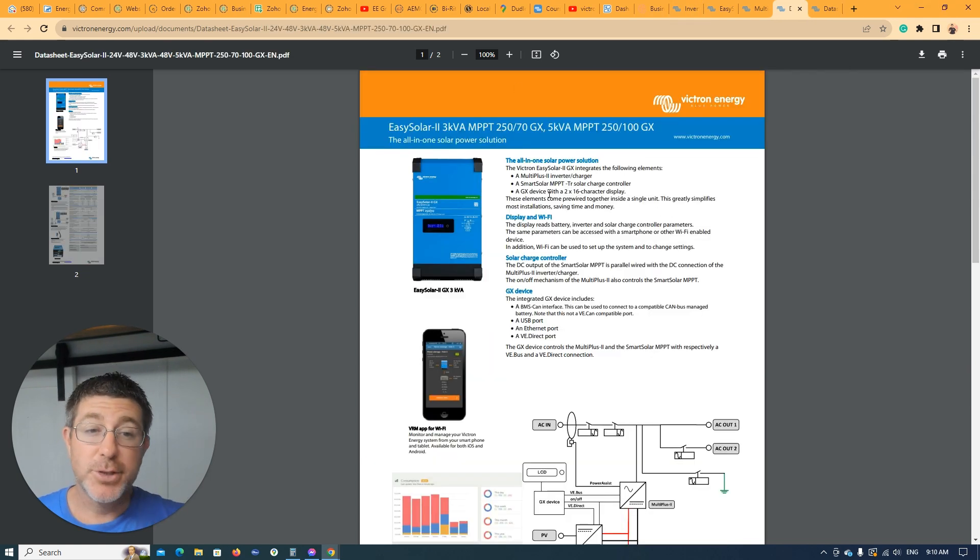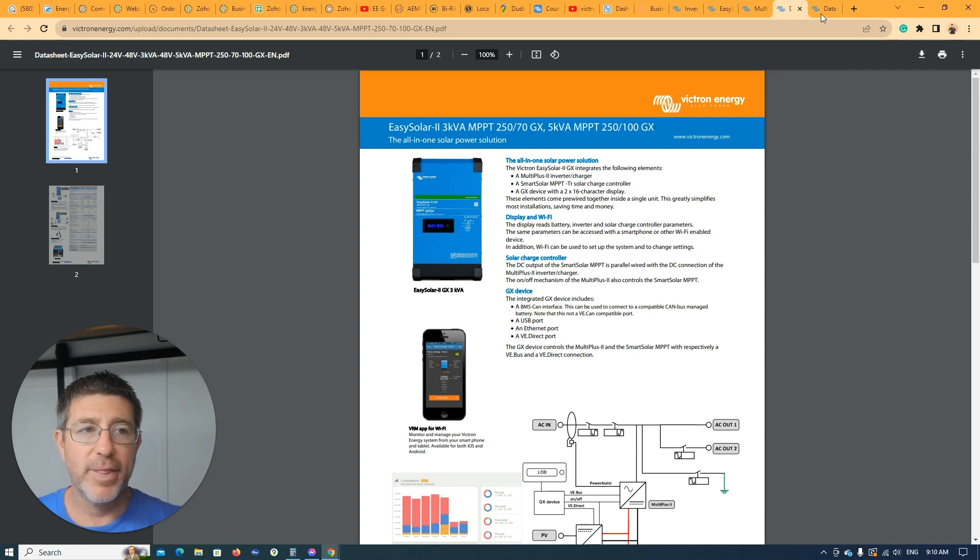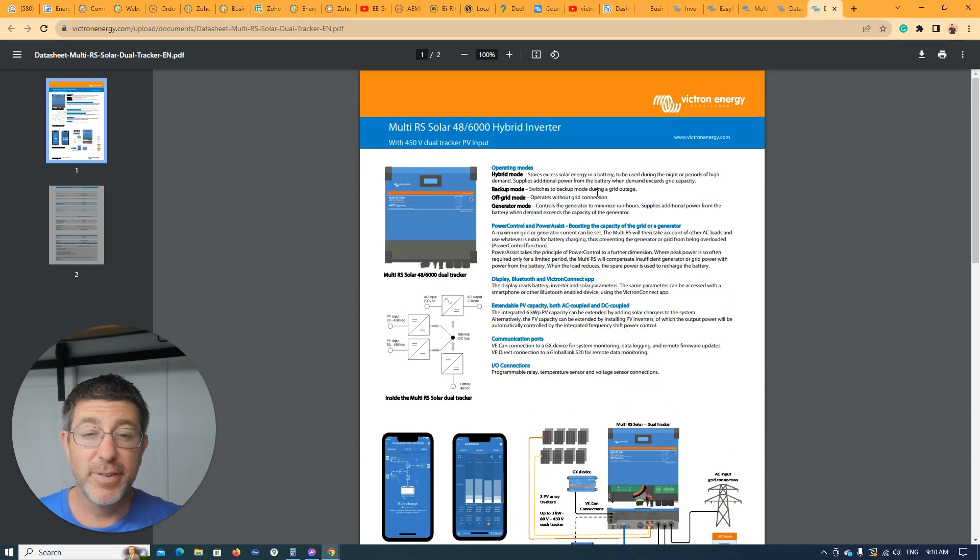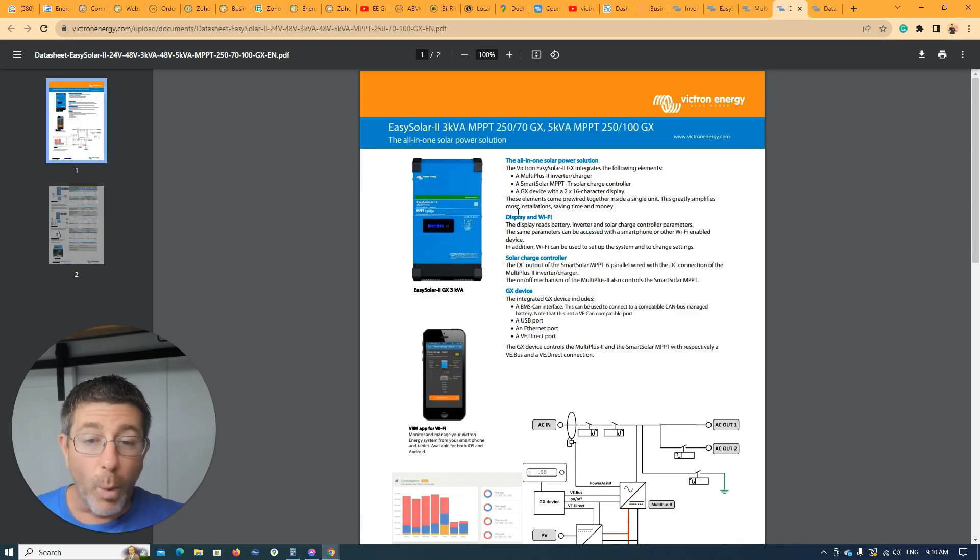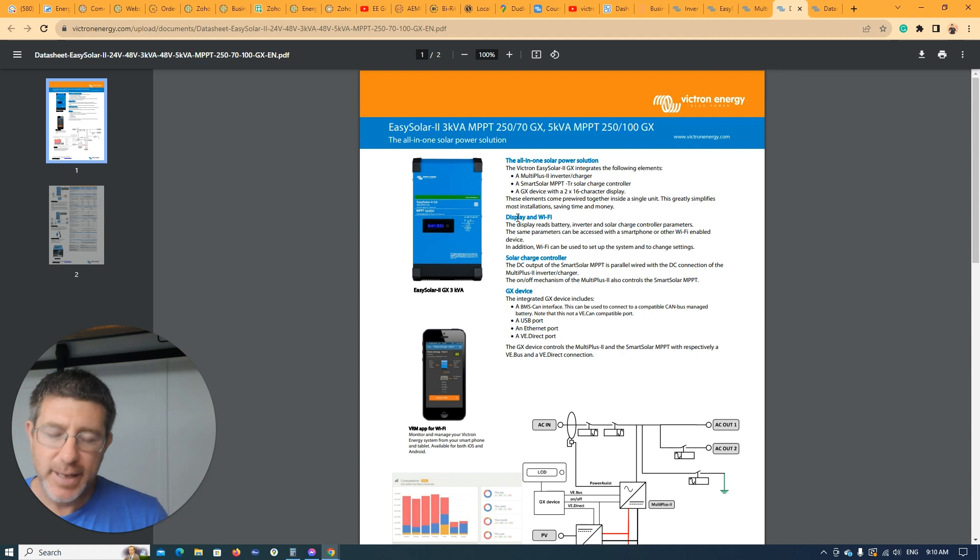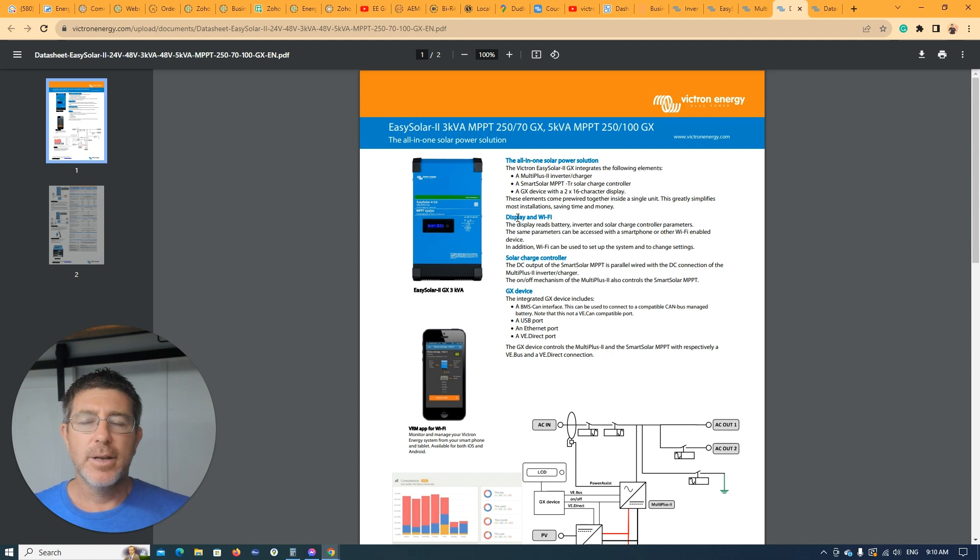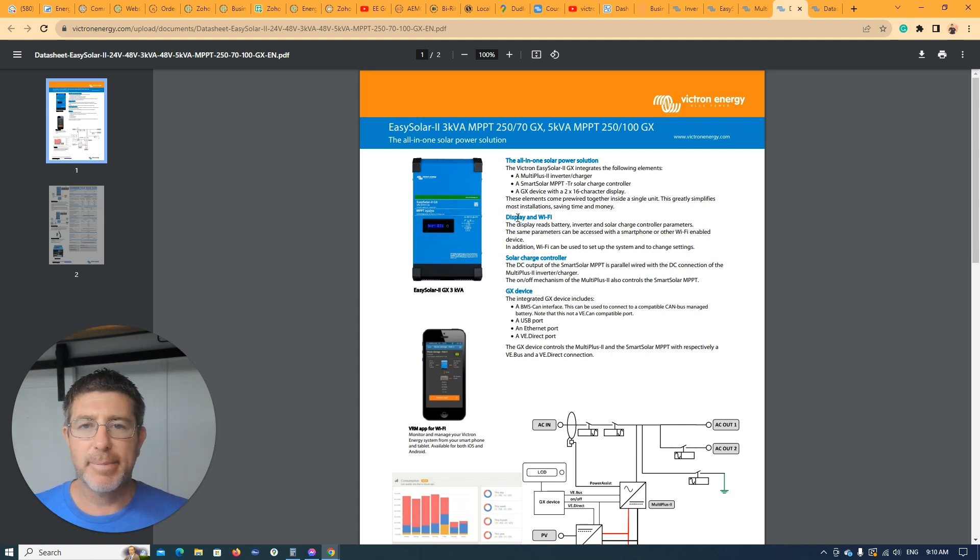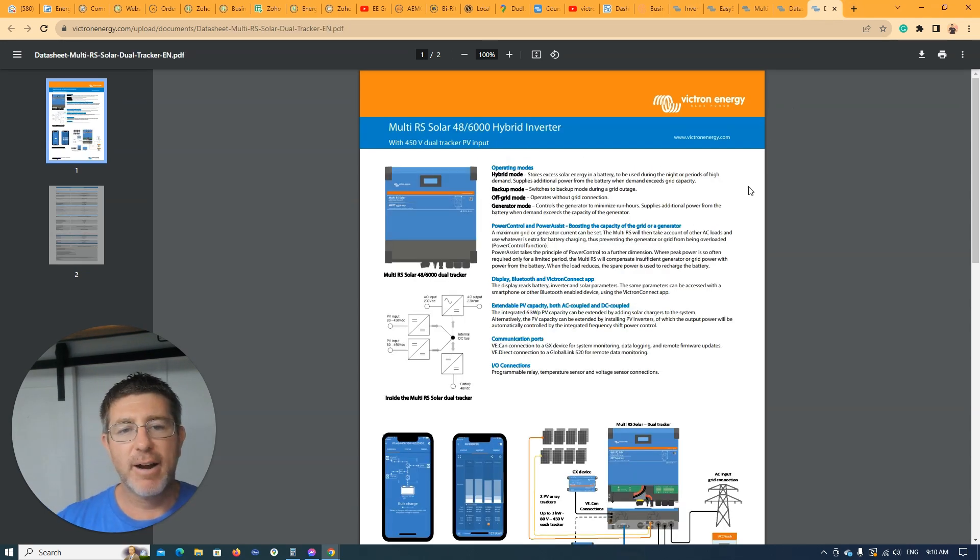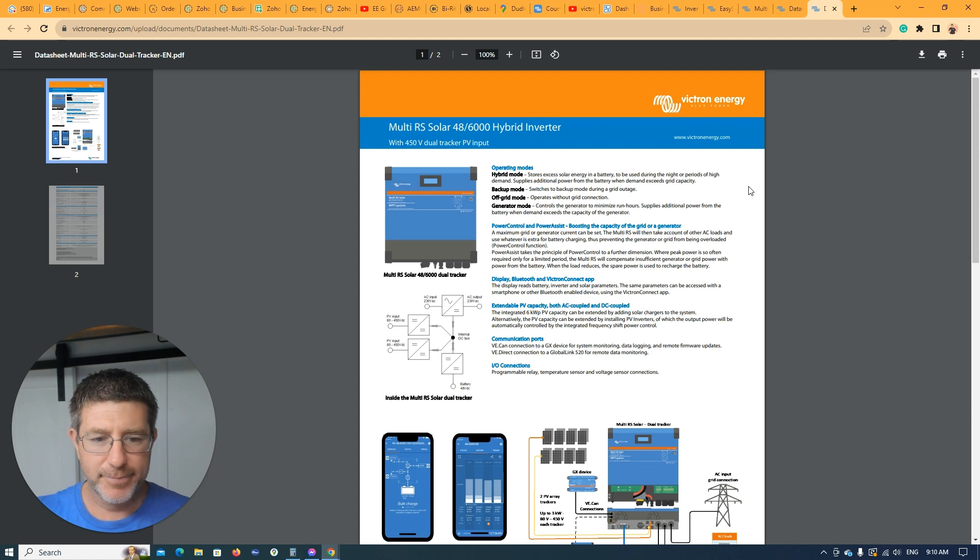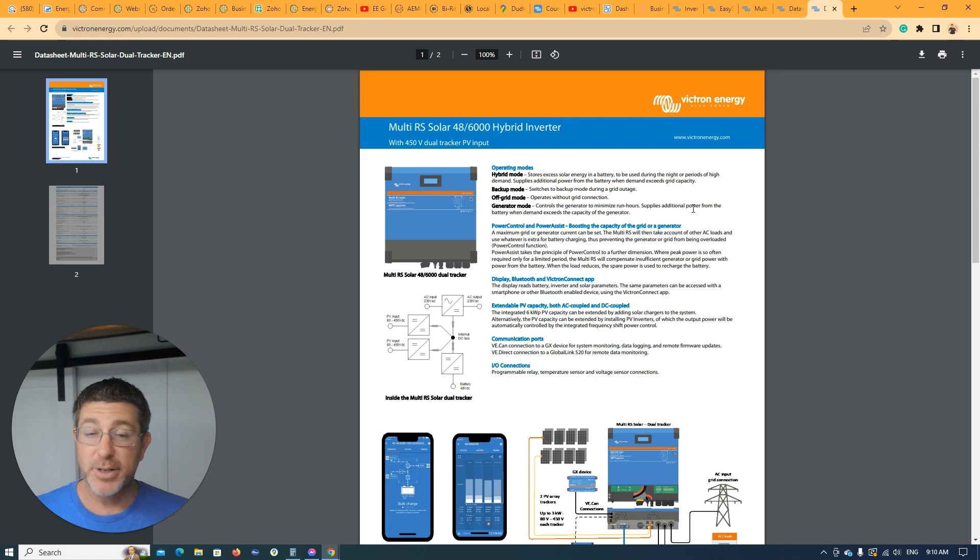As stated before, you can use the 250 volt maximum voltage in there from your solar panels where the RS450 is 450 volt maximum in. What we've done here in the past, we normally just put four solar panels into this one here and then we might put 12, 15 panels into an AC coupling inverter. So it's easy to install on the roof and you've also got panels direct to batteries plus the AC coupling. With these multi-RSs, you can actually still AC couple, which is great. So really depending on what you're doing from an installation point of view is what I'd recommend which one to choose.